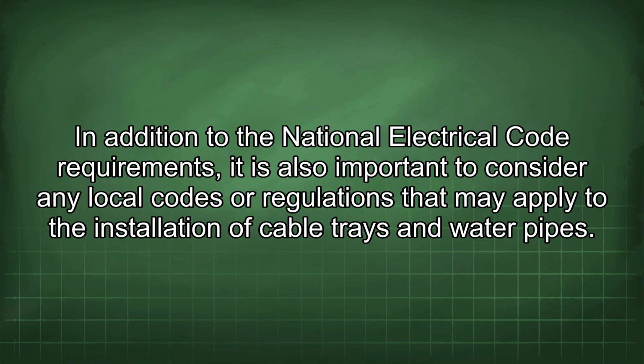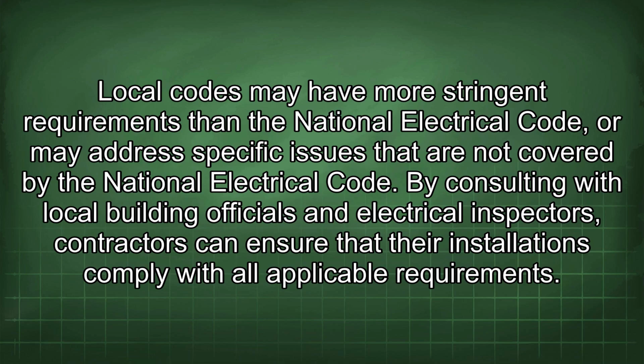In addition to the National Electrical Code requirements, it is also important to consider any local codes or regulations that may apply to the installation of cable trays and water pipes. Local codes may have more stringent requirements than the National Electrical Code, or may address specific issues that are not covered by the National Electrical Code. By consulting with local building officials and electrical inspectors, contractors can ensure that their installations comply with all applicable requirements.